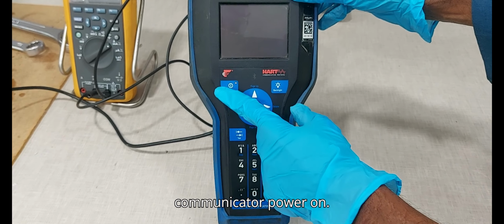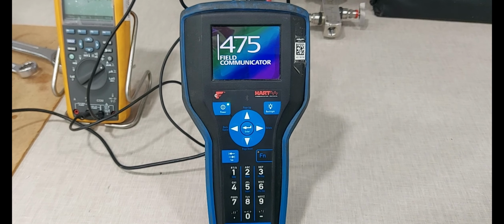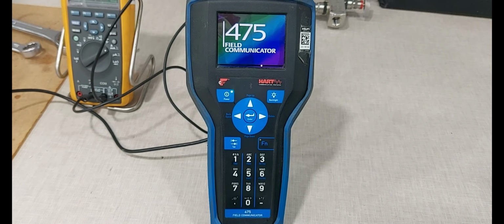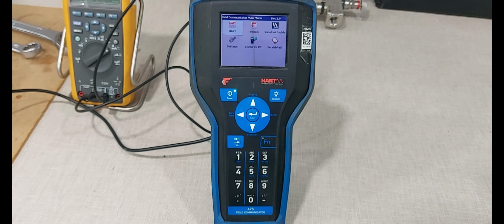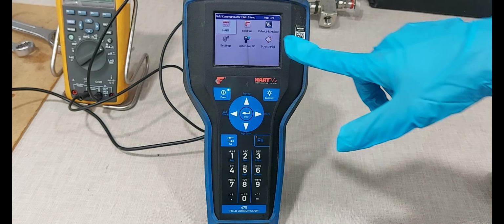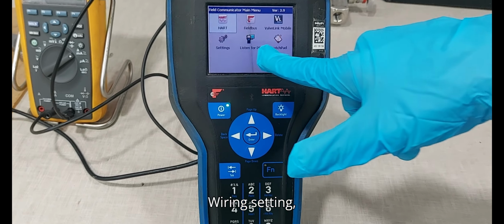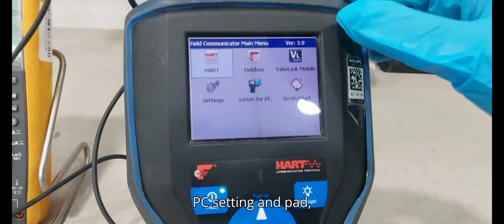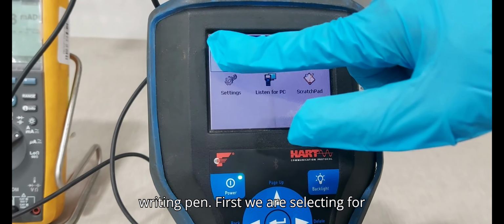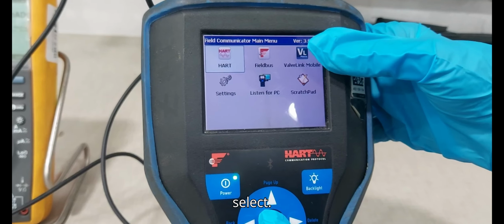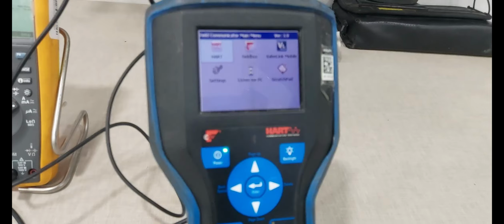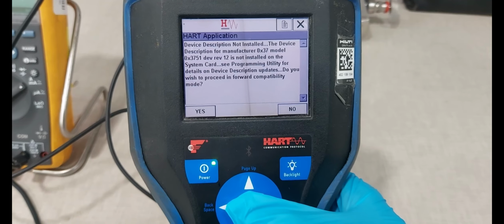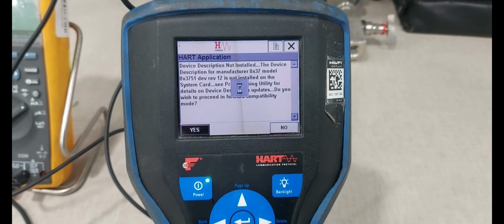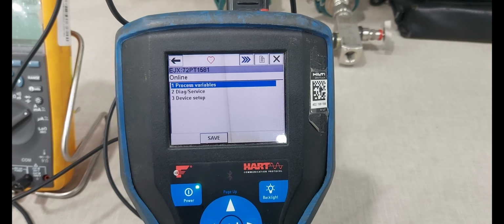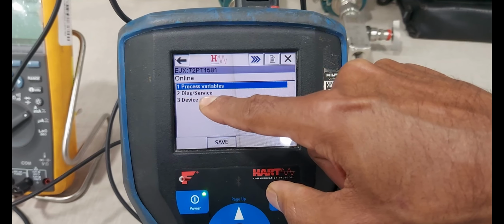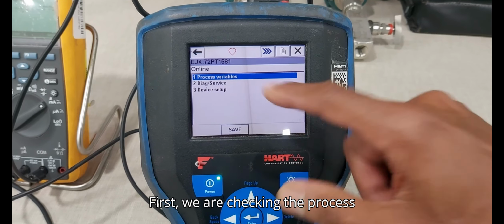Next, power on the field communicator. Now it is on: HART, Foundation Fieldbus, wall link, setting, PC setting and pad, writing pad. First we are selecting the HART communicator. Select. Yes. Online menu: process variable, diagnosis service and device setup. First we are checking the process variable.